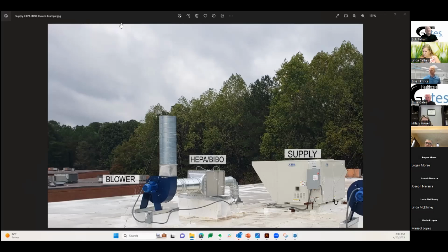I think we missed the most important part of all on sterile environments: the temperature must be 60 to 65 degrees or less, and humidity must be under 60% RH. You do not buy a commercial office unit that can do that. You have to reheat the system at the very best to drain out the amount of moisture. So there again is the cost—that is hugely expensive because it is not a standard unit, it has to be custom made. I think that was really important to say.